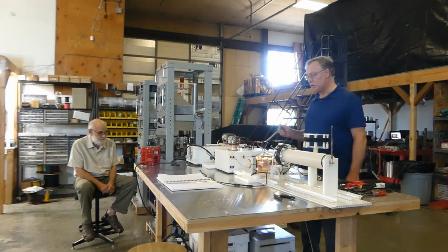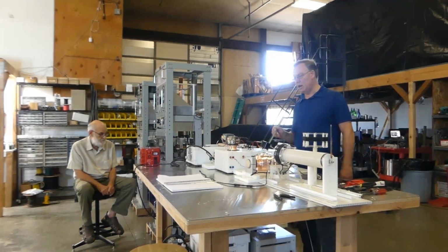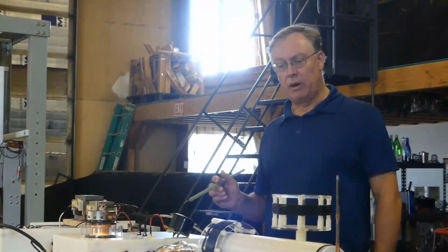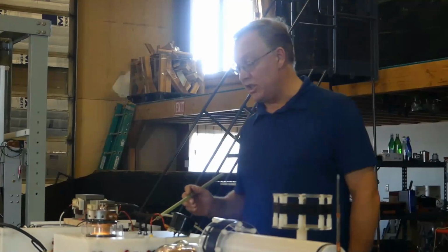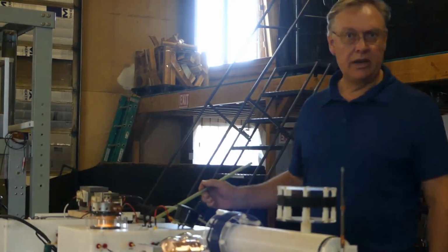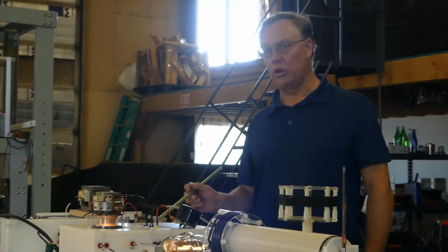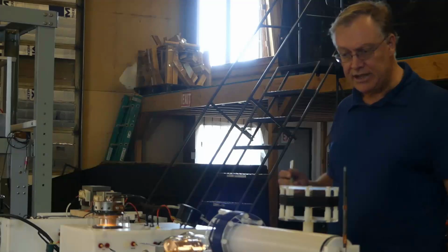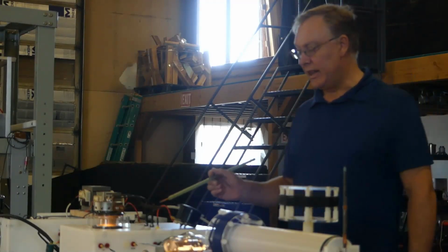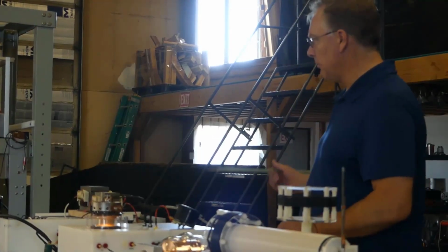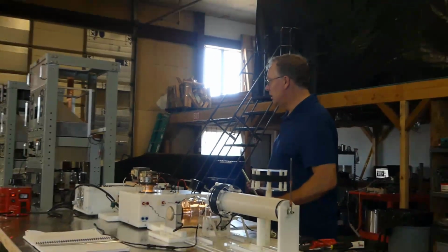Okay. And then just to add, what we did to initially test that system was we first of all measured the open circuit cathode voltage to make sure it is not too much for the relays. All that means is disconnecting one side of the cathode from ground and measuring that open circuit voltage on the cathode to ground, with everything set as it would be when you were running. That measured at 158 volts. What is the maximum that the relays can take? I wouldn't go above 300.